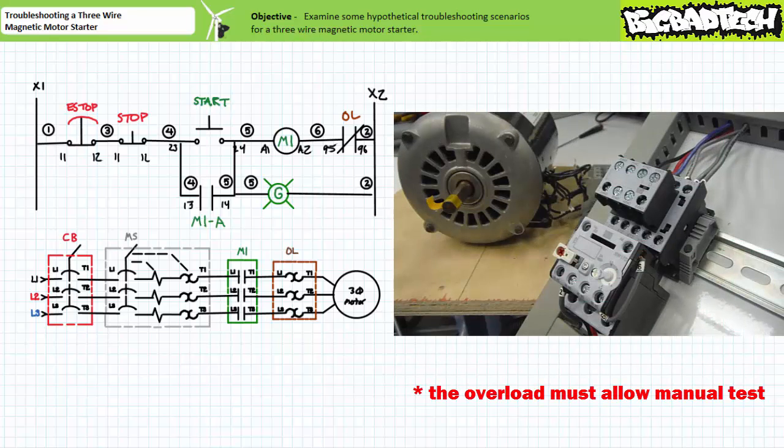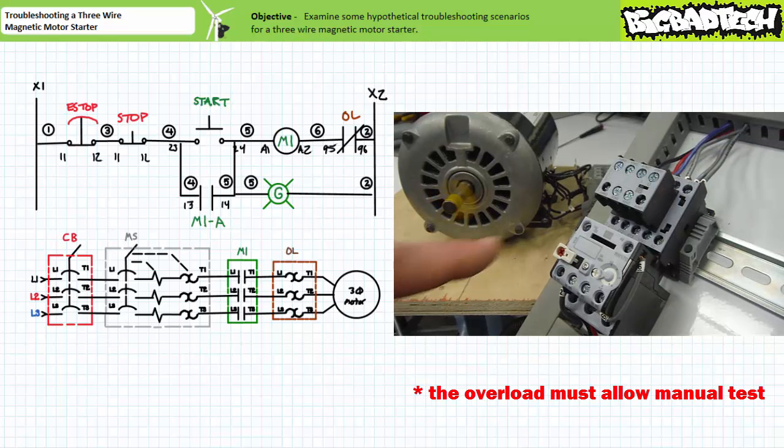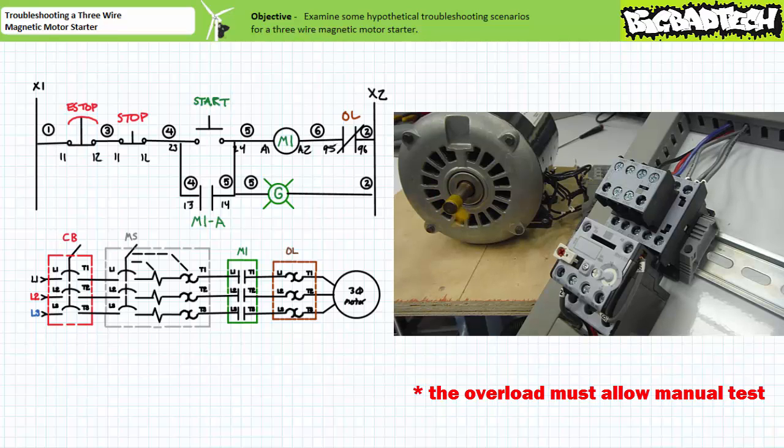The easy answer is to quite simply de-energize the contactor coil. The most immediately accessible means of doing so is to manually trigger the overload test button on the front of the overload relay. When the overload is manually triggered, the contactor coil is de-energized, the holding circuit is broken and the motor free spins to a halt.